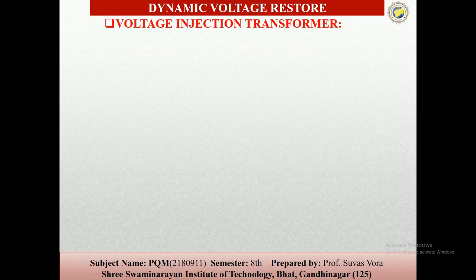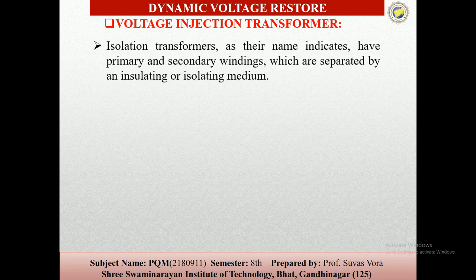There are three single phase transformers that can be coupled to the distribution line, with a star connection in the primary winding and an open star winding in the secondary winding, or a delta connection in the primary winding and an open star connection in the secondary winding. Basically this is called the isolation transformer, and as the name indicates, it has primary and secondary windings which are separated by an insulating or isolating medium. The former allows the injection of positive, negative and zero sequence voltage, while the latter allows only the injection of positive and negative voltage.